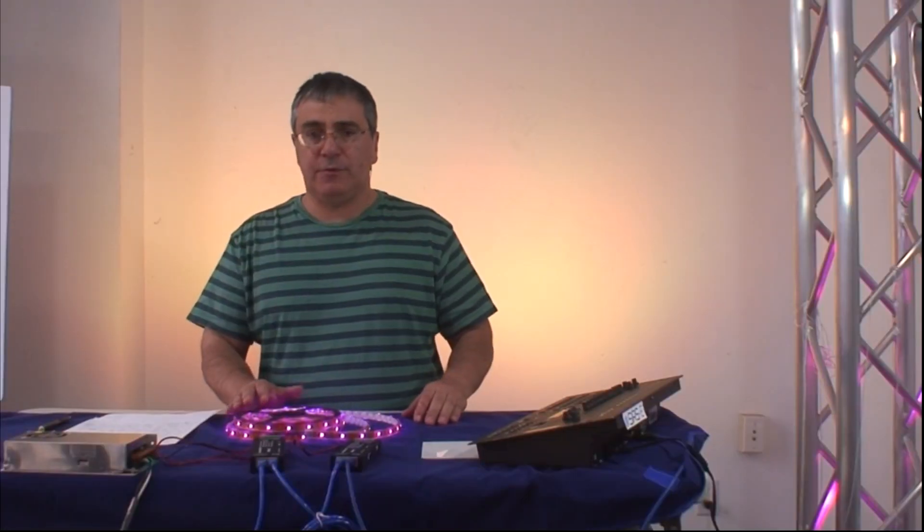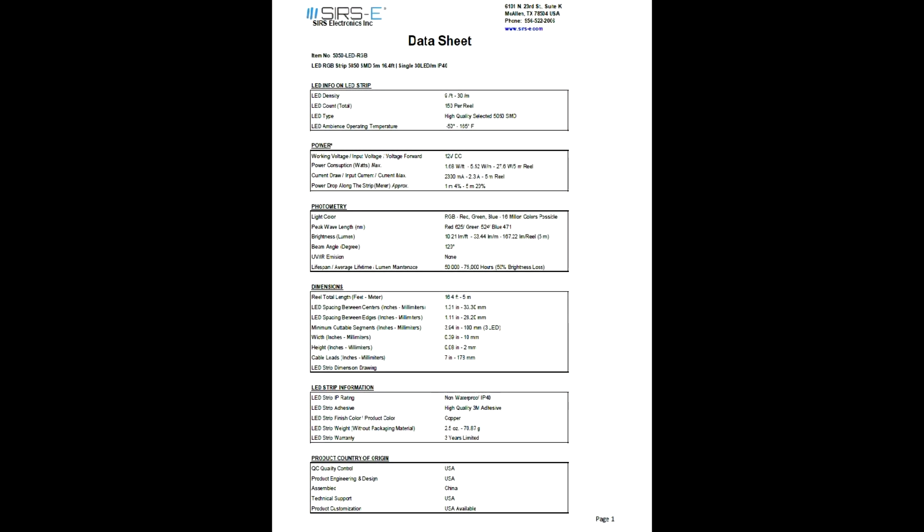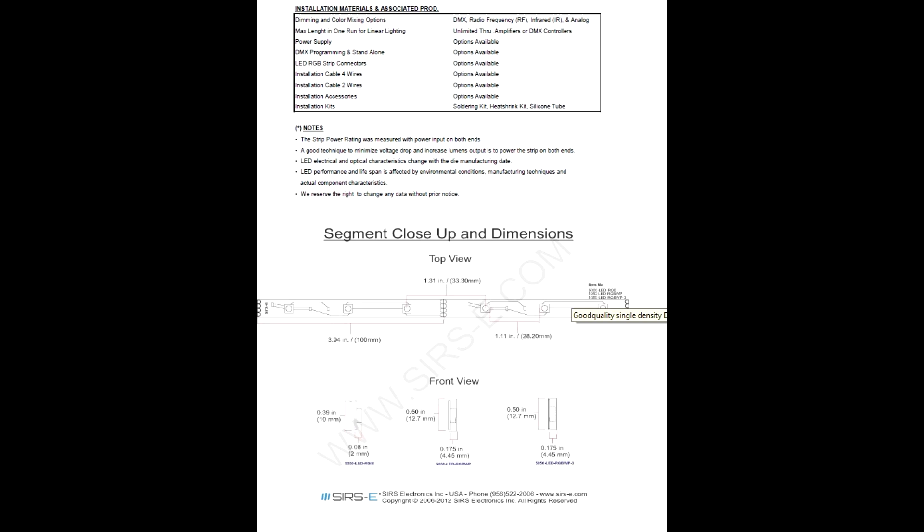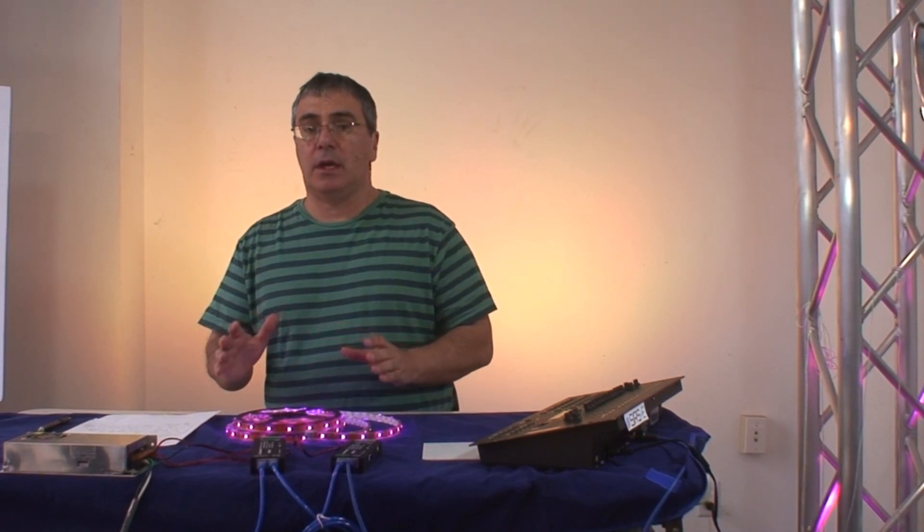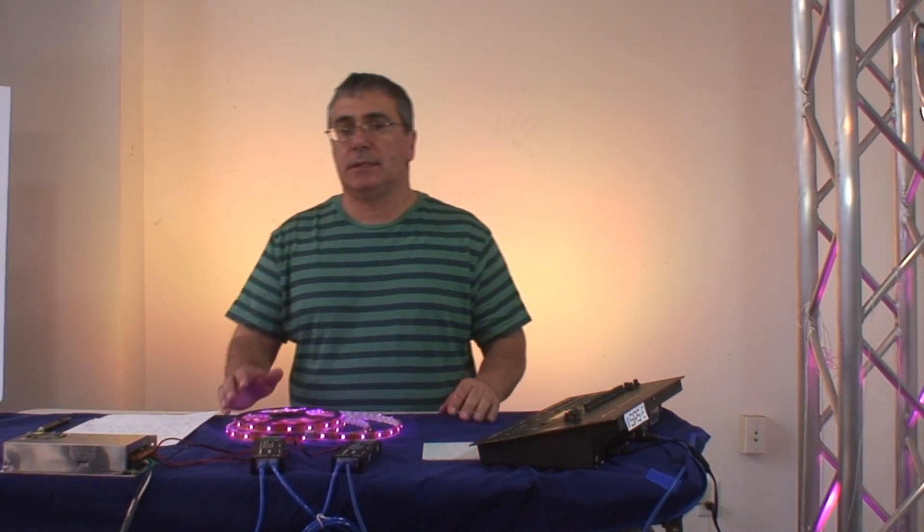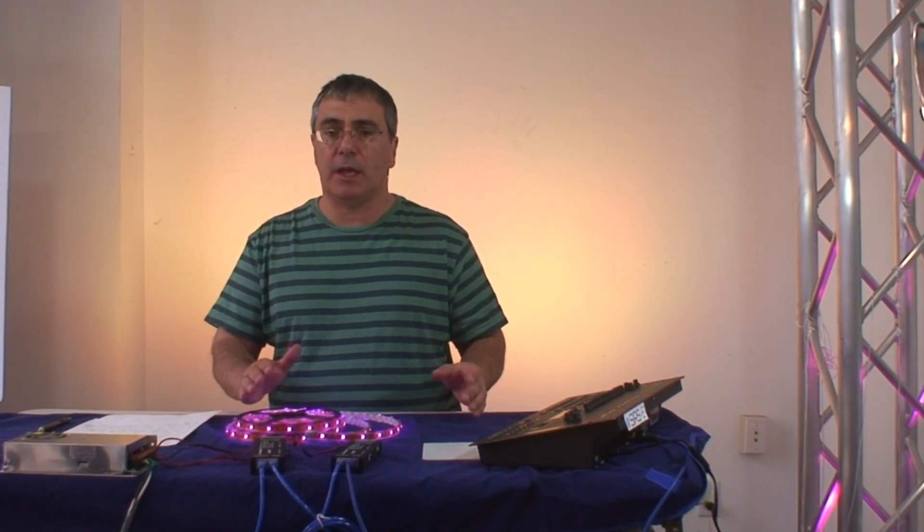With that information we prepare a data sheet that we send to the manufacturer with all the electrical, optical characteristics that the product should have. Once they finish the batch of the manufacturing, they test the strips and will compare if they pass or not.